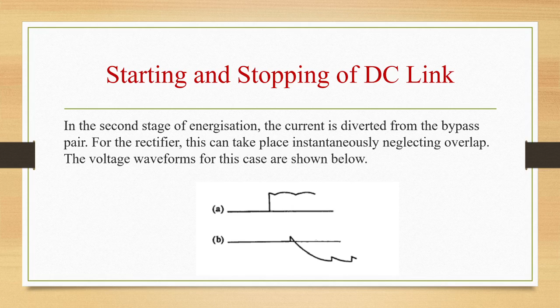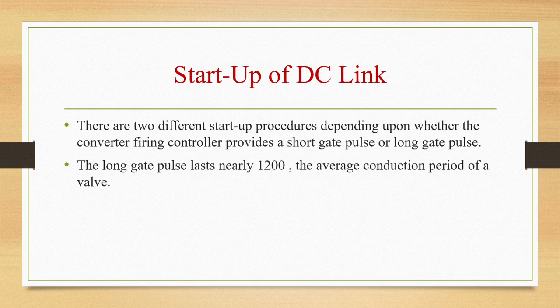There are two different startup procedures depending upon whether the converter firing controller provides a short gate pulse or a long gate pulse. The long gate pulse lasts nearly 120 degrees, which is the average conduction period of a valve. Let us see the startup with long pulse firing. In this case, current extinction during the startup is not a problem.